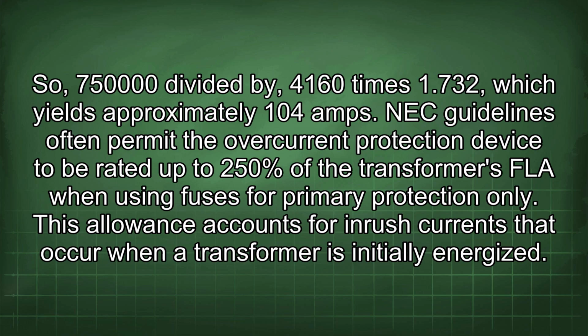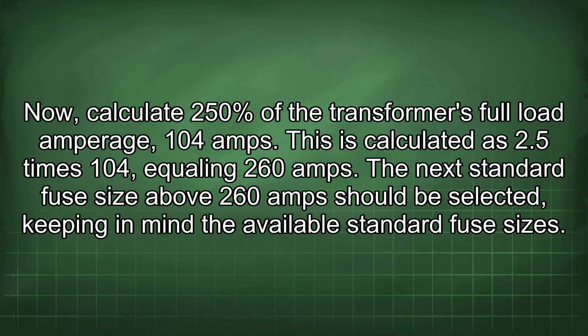NEC guidelines often permit the overcurrent protection device to be rated up to 250% of the transformer's FLA when using fuses for primary protection only. This allowance accounts for inrush currents that occur when a transformer is initially energized. Now calculate 250% of the transformer's full load amperage, 104 amps. This is calculated as 2.5 times 104 equaling 260 amps.